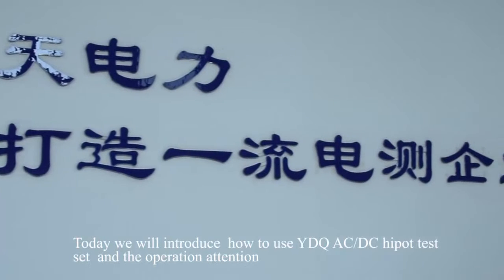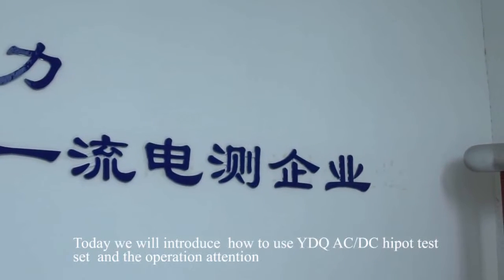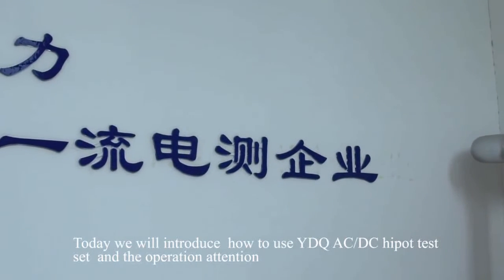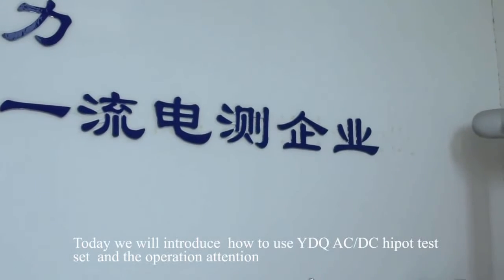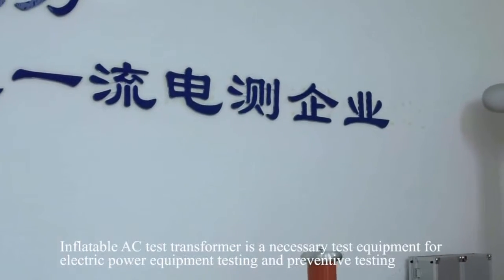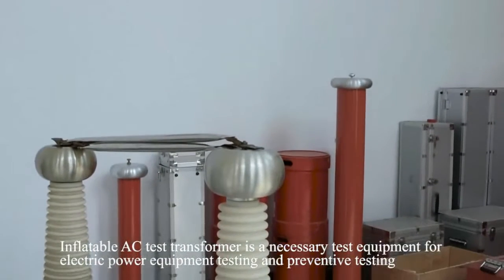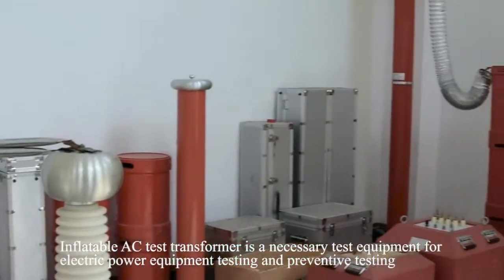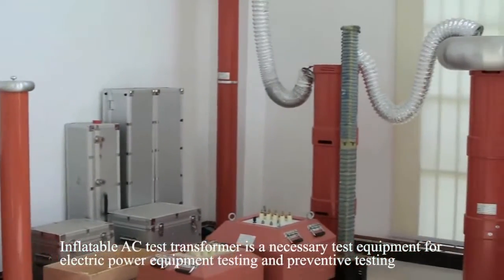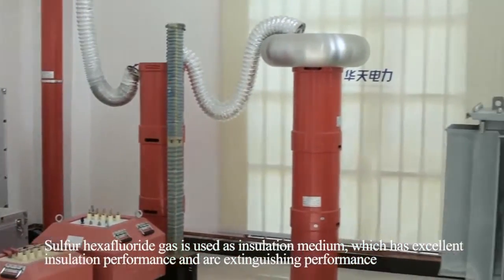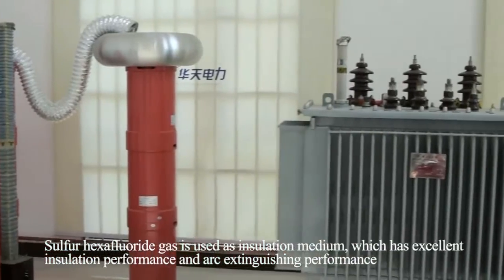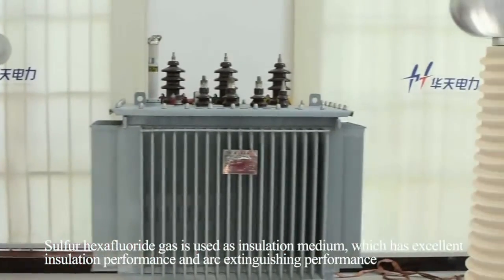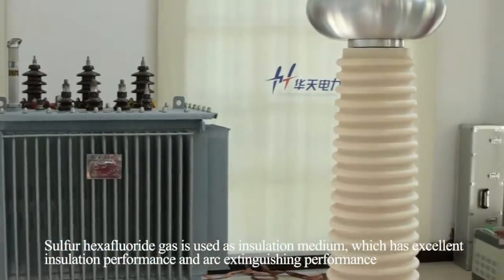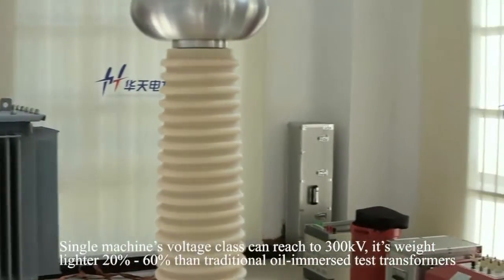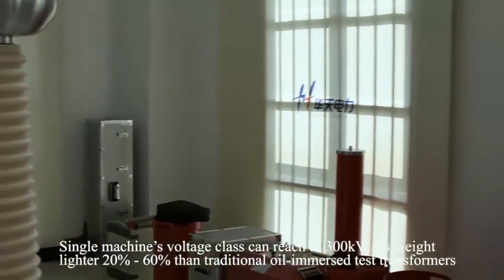Today we will introduce how to use the YDQ AC/DC Hipot test set, gas type, and its operation and attention points. The inflatable AC test transformer is necessary test equipment for electric power equipment testing and preventive testing. Sulfur hexafluoride gas is used as the insulation medium, which has excellent insulation and arc extinguishing performance. The single machine voltage class can reach 300 kV.